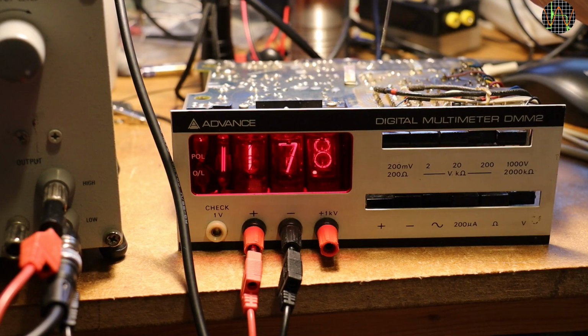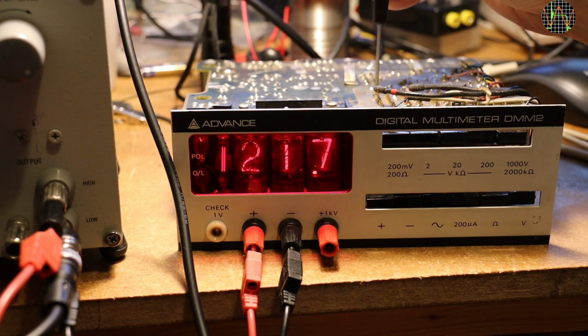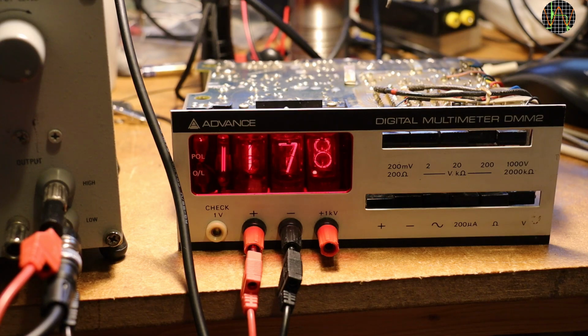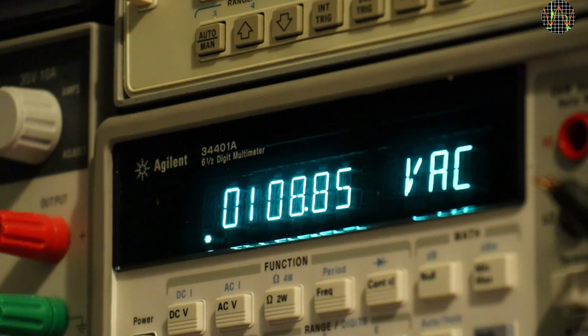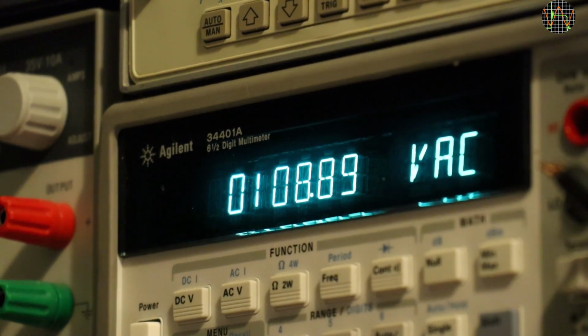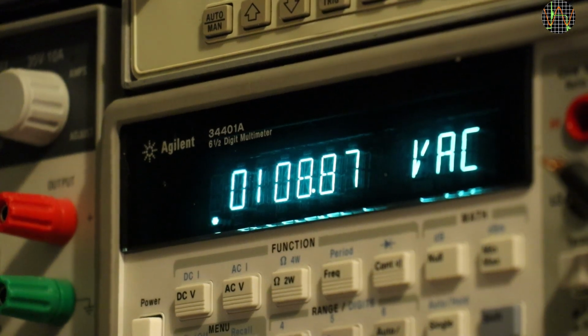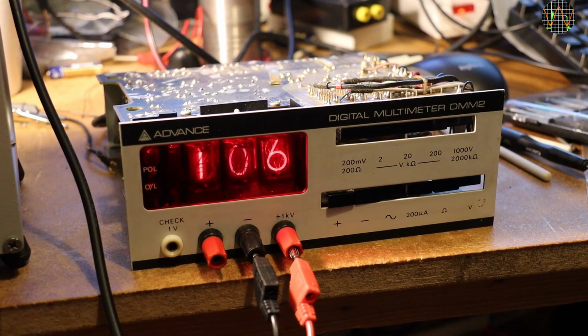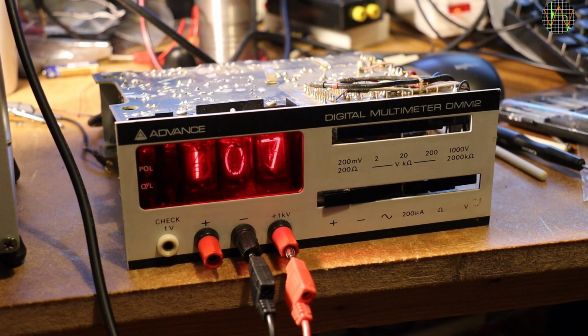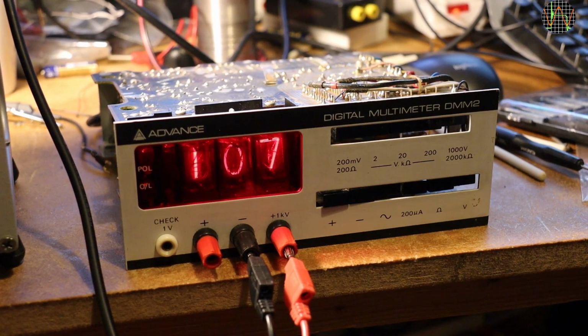I don't have a good way of producing a stable 200 volts at 20 kHz. So for this one I just use 119 volts at 10 kHz. You can see what I mean. As soon as the metal screwdriver goes in, the value changes and changes again when the screwdriver is removed. So you're basically adjusting in a trial and error way. For the 1000 volts, I use just 108.8 volts AC at 5 kHz, but I'm not going to calibrate, just check. Between 106 and 107 volts, I think that's close enough.